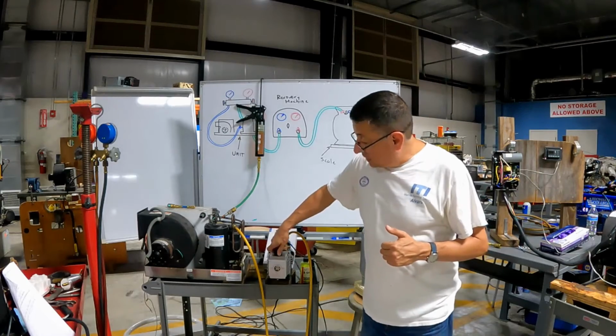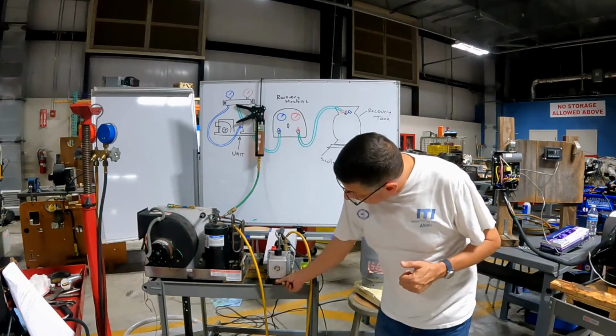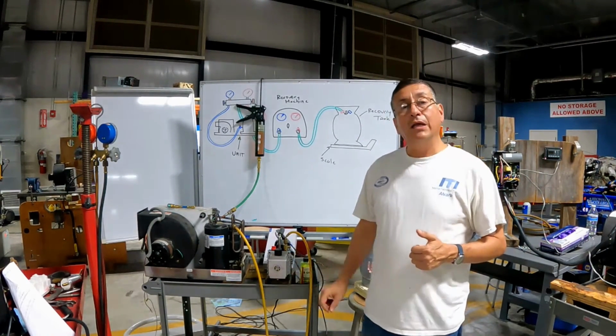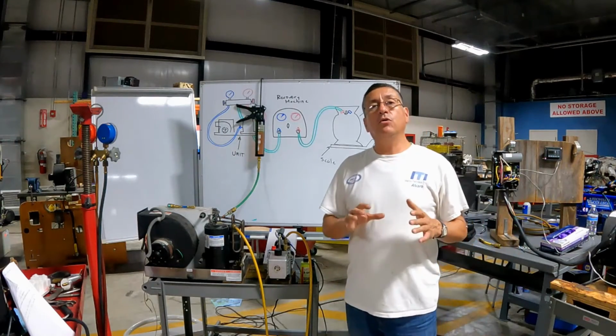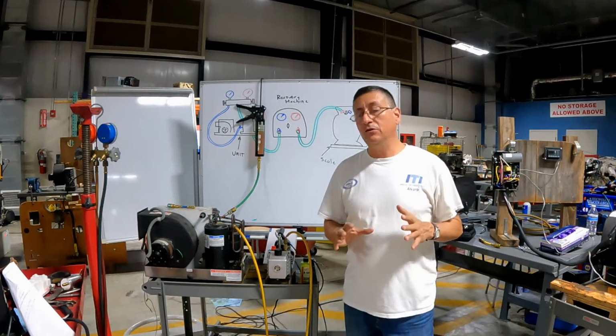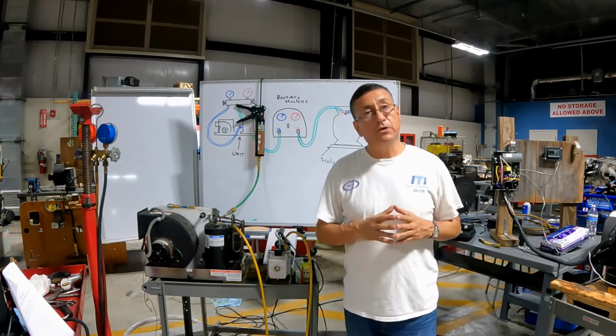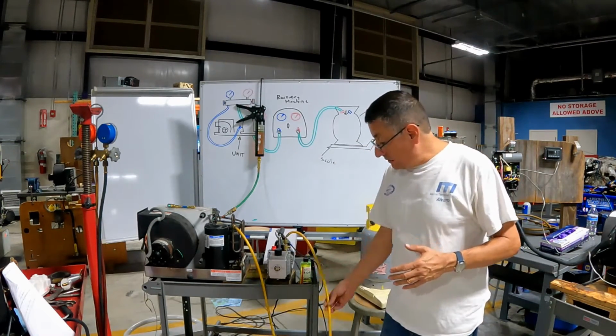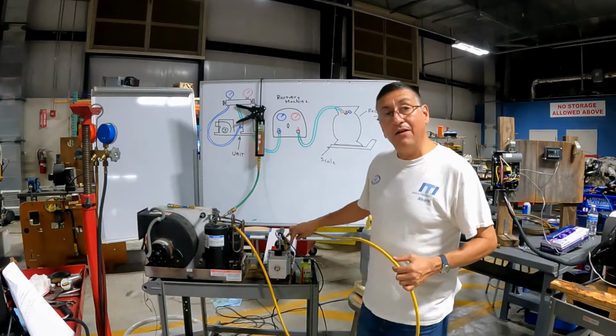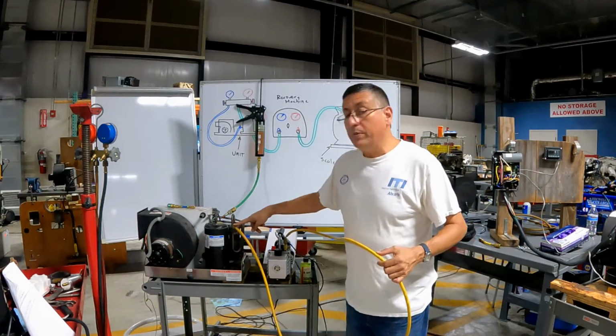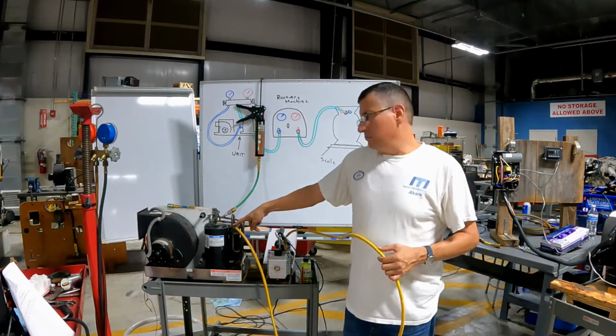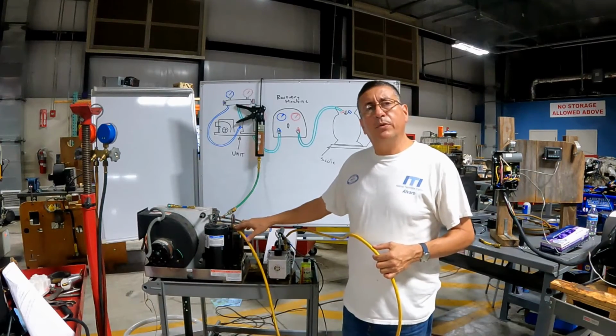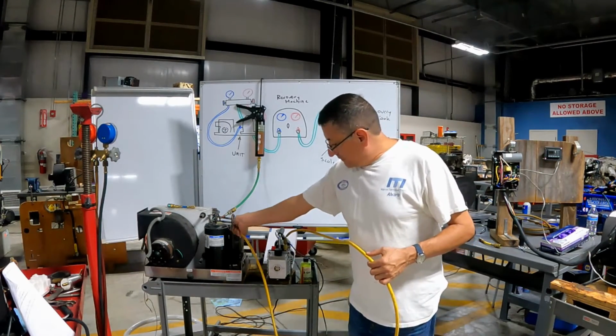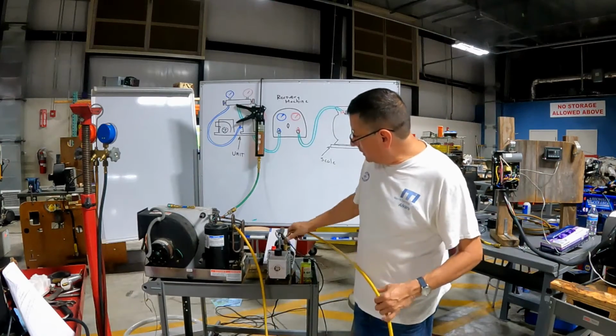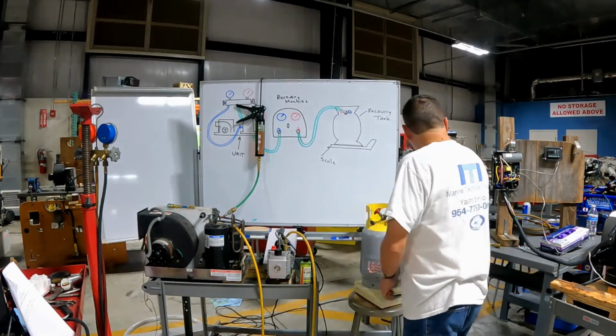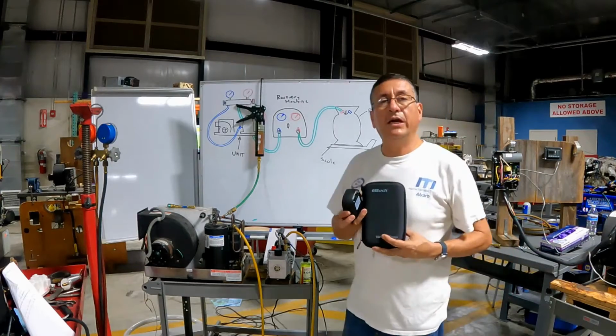And it's easy: you open here, drain the oil at the bottom, and replace it. Keep the oil in good condition. This is the recommendation for those specific pumps. Okay, you need a line to connect the valve of the pump with the low pressure side of the equipment. You can use any part of the low pressure side. And yes, you have the line connected on the low pressure side. And I also recommend a vacuum gauge.